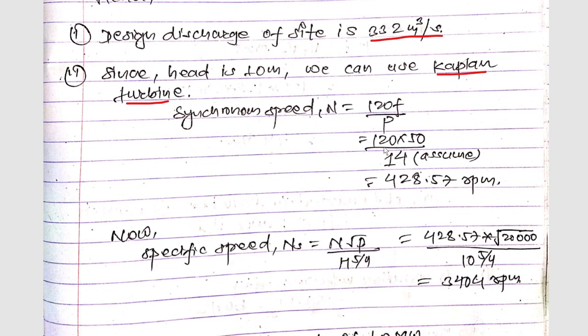The formula to calculate synchronous speed is N = 120f/P. With 120 × 50 / 14, assuming the pole value as 14, we get the synchronous speed as 428.57 rpm.